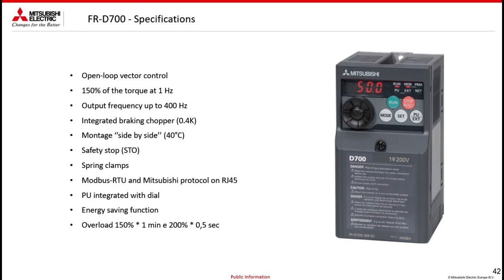Overload 150% for 1 minute and 200% for half a second of the nominal current. This is important because, for example, to lift a vertical load, the gravity force will require a current higher than the motor nominal, and therefore it could get close to the inverter nominal, and this function allows you to go further to overcome this force to move this load.